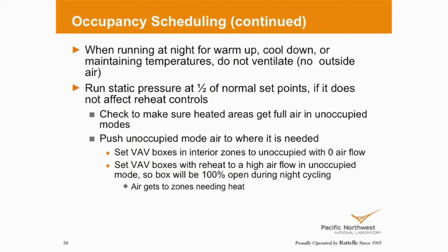Why did they set up the perimeter boxes? Because that's where the skin of the building is. That's where you're infiltrating potentially. If you can maintain the perimeter of your building, you're going to maintain the core. So we've done this a lot. In a lot of our buildings, with rooftop units, if you've got a smaller building with rooftop units and it's zoned, so you've got perimeter zones and interior zones, we shut off the interior zones, we worry about the perimeter.